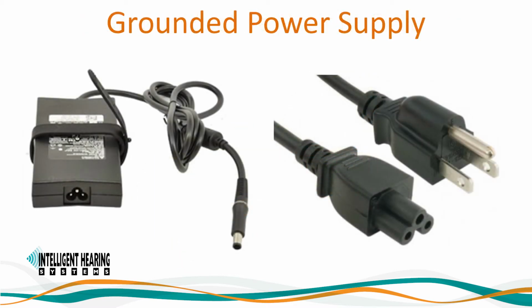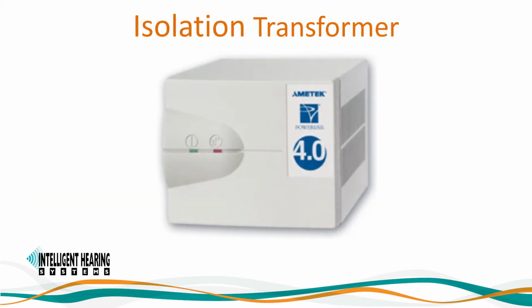Computers must have a 3-prong grounded power supply and cable. If interference occurs during testing and you are using a laptop computer with a built-in battery, then try running the laptop on battery, disconnected from its power supply. Ensure that the battery charge is adequate to complete the test. When using a medical-grade power isolation transformer, make sure it is connected to an earth-grounded outlet. All interconnected equipment, even if switched off, should be connected to this transformer.